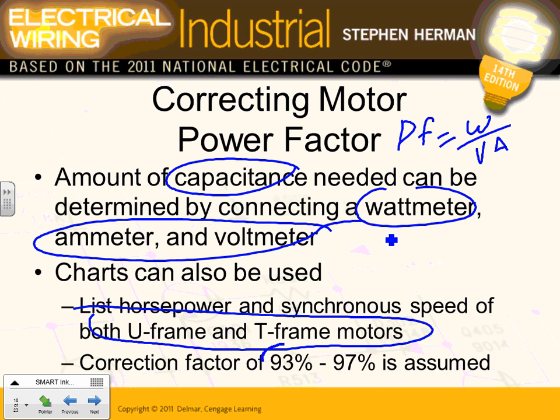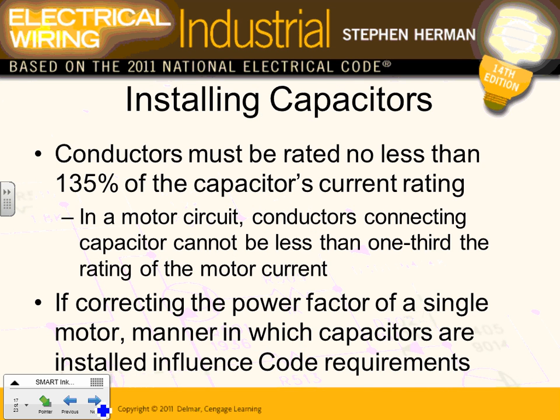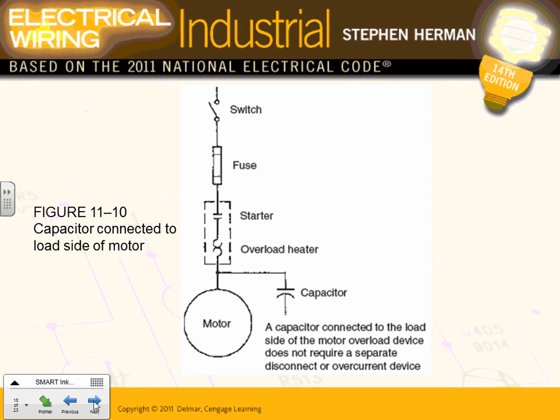When you correct, you always correct not to 100%, but between 93 to 97%, because you don't want to end up with a leading power factor. Okay, so when you have a capacitor, guys, there are two ways of connecting it.